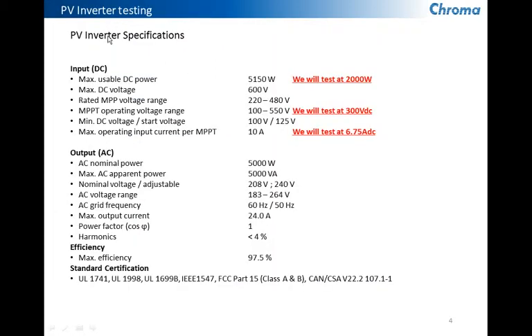When you look at the inverter or PV inverter specification it has some definite definitions for maximum usable DC power. It also has a maximum power point operating voltage range and a maximum operating input current. So with this setup that I'm going to run I'm going to use 2,000 watts as my maximum power, 300 volts as our voltage at maximum power and 6.75 amps as the current at maximum power.